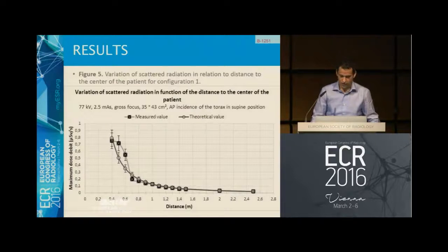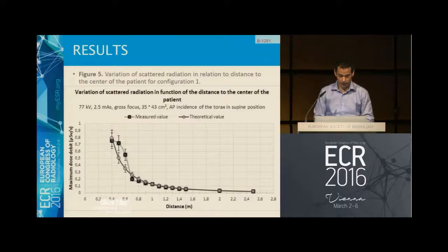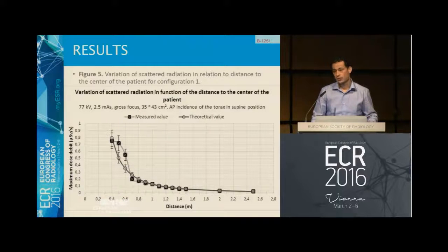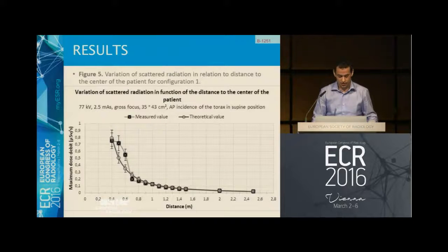We also performed the variation of scattered radiation in relation to distance to the center of the patient for configuration one. Here we have the theoretical value and here the measured value. These differences are hypothesized to relate to the anthropometric characteristics of the patient — the measured value never corresponds exactly to the theoretical value.